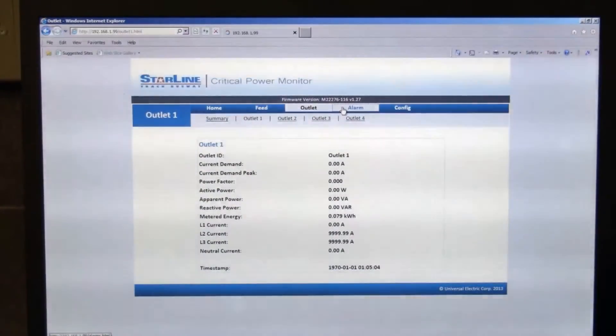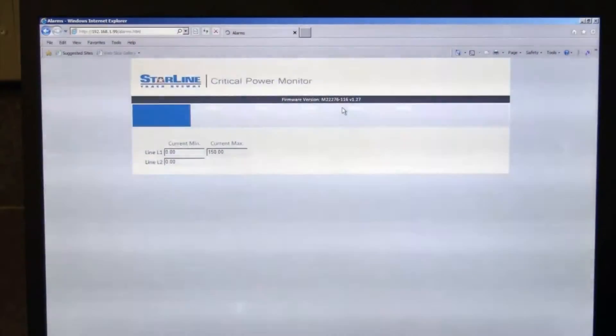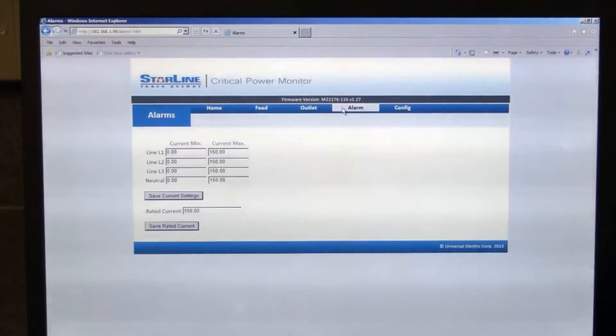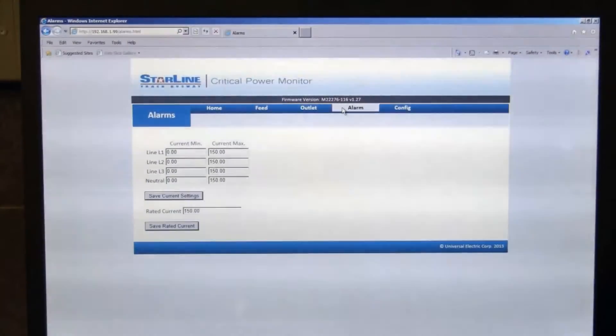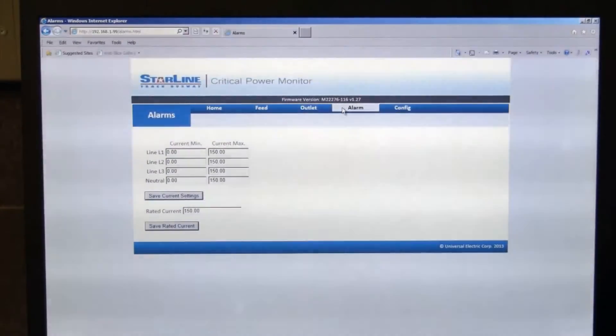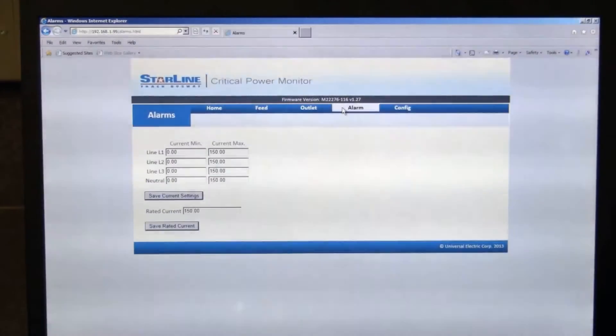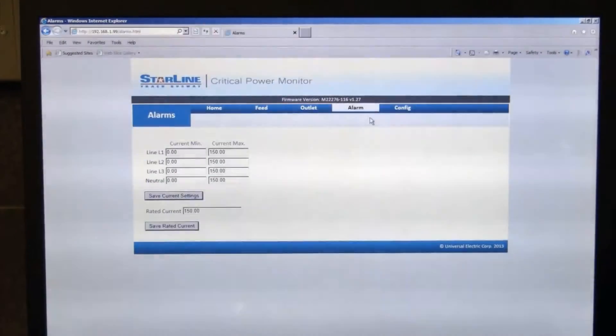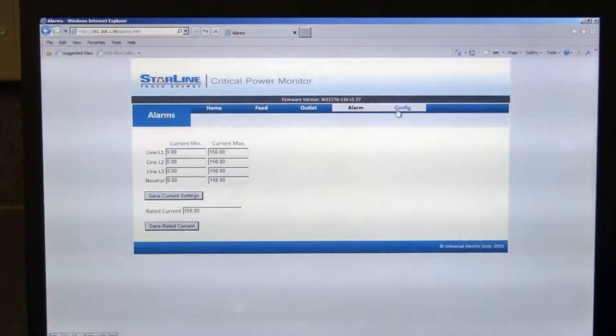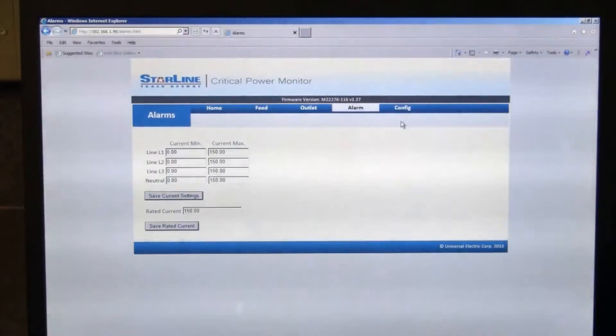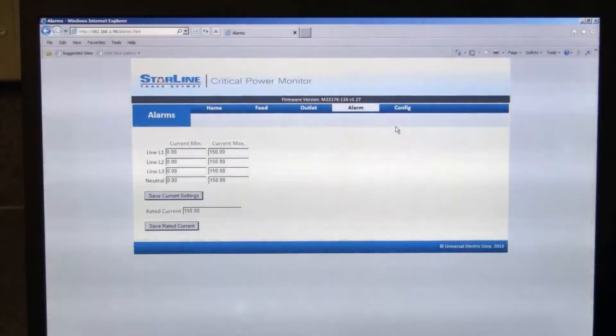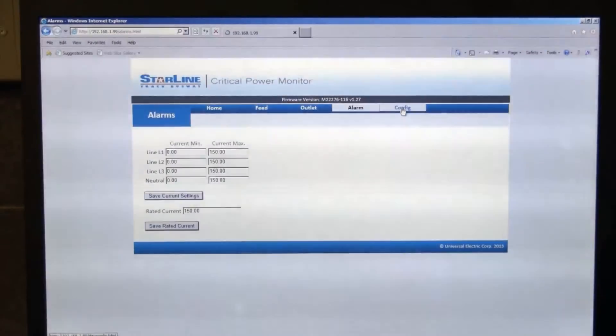The next tab is the alarms tab. You can actually set min and max values and save those settings, and then you can be notified via SNMP traps or email notification if you exceed a min or max alarm condition, which I'll show you how to set up here in a minute.